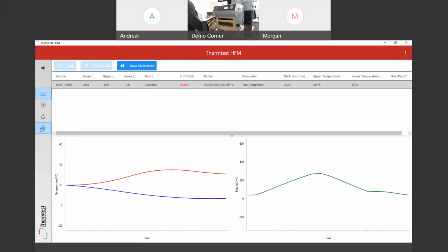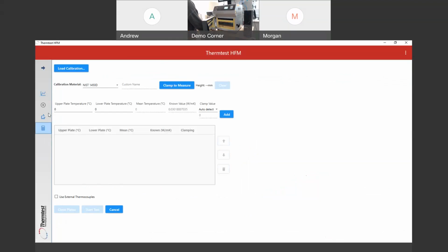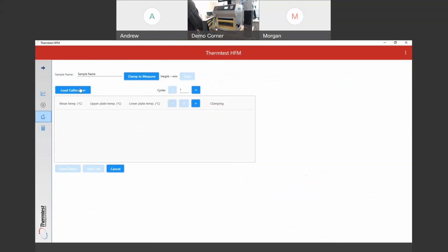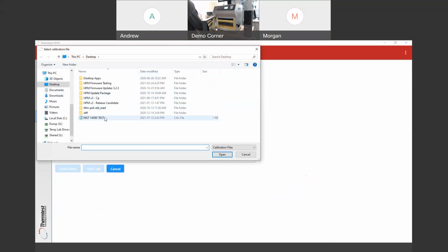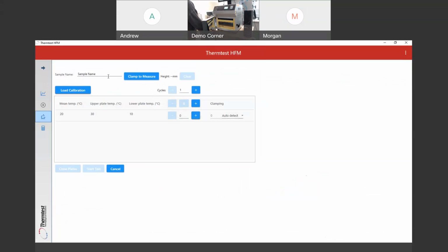Once it's done, the plate opening. So if you're in test mode, oh, sorry, here's test mode. So here you can load your calibration. Let's say this is it. That would be the name of your sample. You could again close the plate, rather, you could close the plate to a specific thickness. So let's say you're doing a batting insulation that's really soft, and you want to test it at 25 millimeters and not let it compress smaller. You could just put that value right in here.